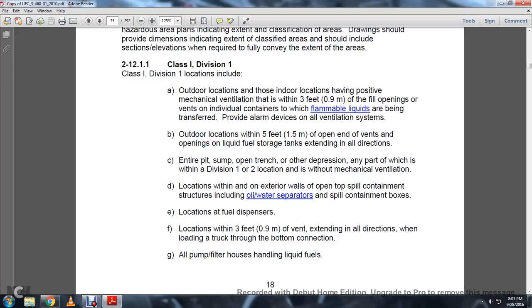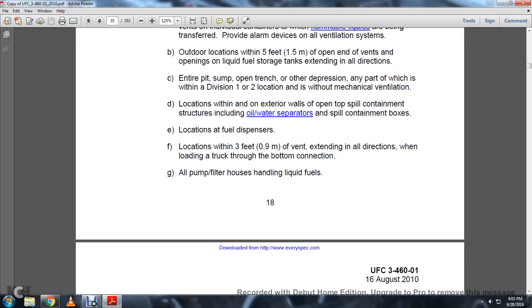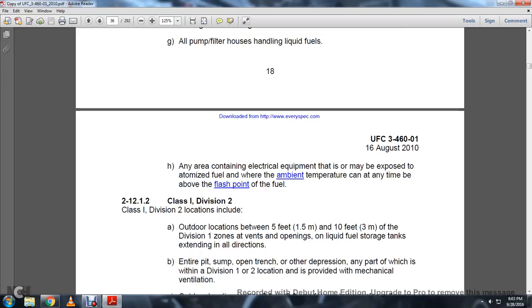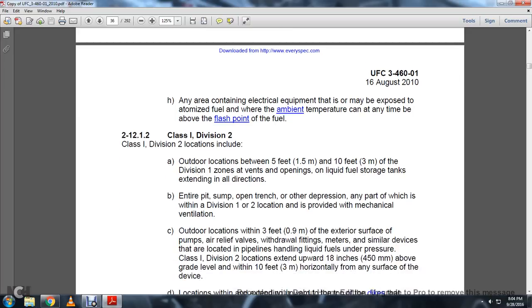of the vents, open liquid storage tanks, extended in all directions; an entire pit, sump, trench, or other depression, any part of which is in a Division 1 or 2 location, without mechanical ventilation; locations within the exterior walls to the open top of spill containment structures, including oil water separators and spill containment boxes; locations at fuel dispensers; locations within 3 feet of the vent extending in all directions when loading trucks at the bottom connection; all pump and filter houses handling liquid fuels; and any area containing electrical equipment that is or may be exposed to atomized fuel and where ambient temperature can be at any time above the flash point of the fuel.